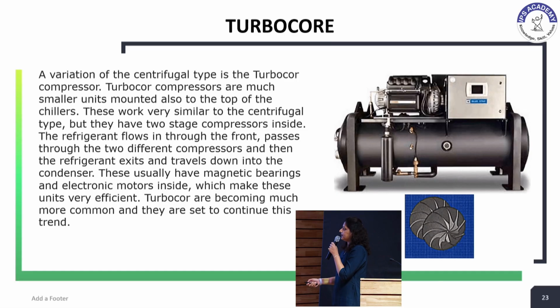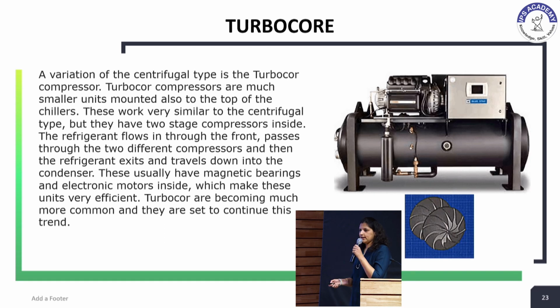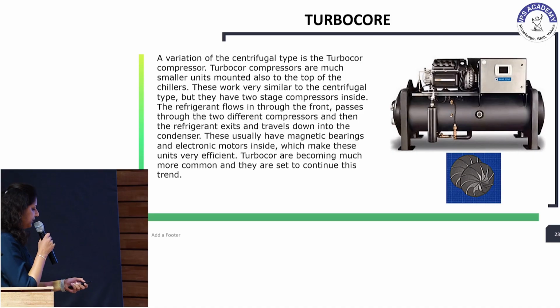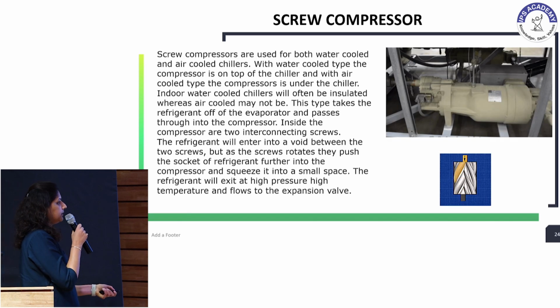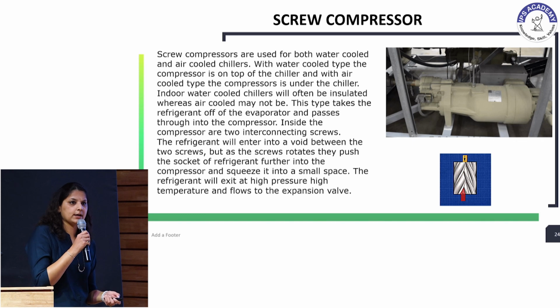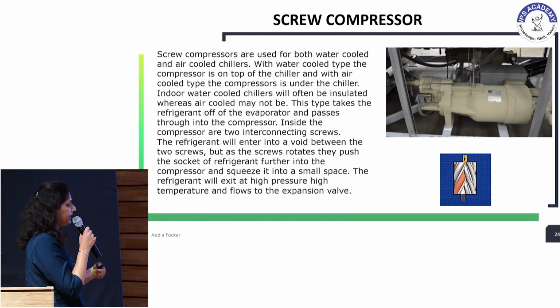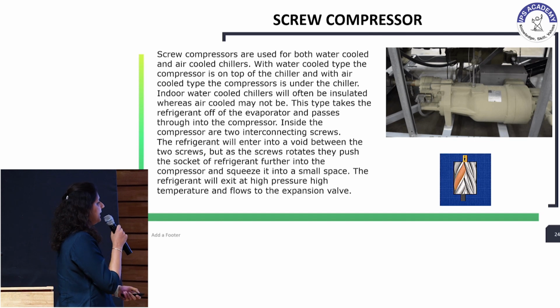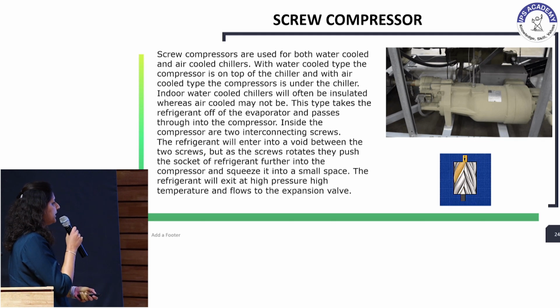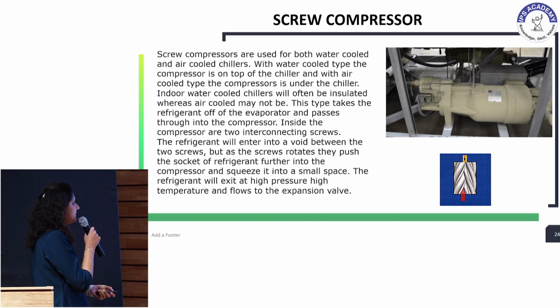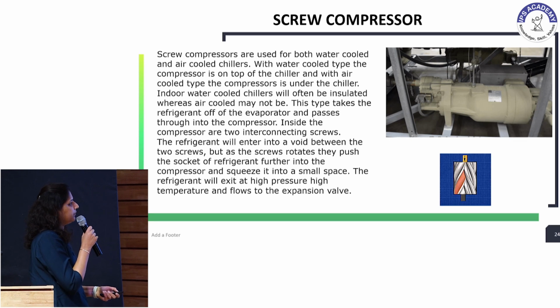Then we have a turbocore compressor which is also a family of centrifugal compressor. The only difference is it has two stages of compression. So normally what you see different in a turbocore is that it has magnetic bearing and electronic motors which make it more efficient than a centrifugal compressor. Then screw compressors, which are age-long technology which have been in the market and have been evolving since they came. They have two rotors which actually run with each other to compress the gas, and the compressed gas is then flowed to the condenser.